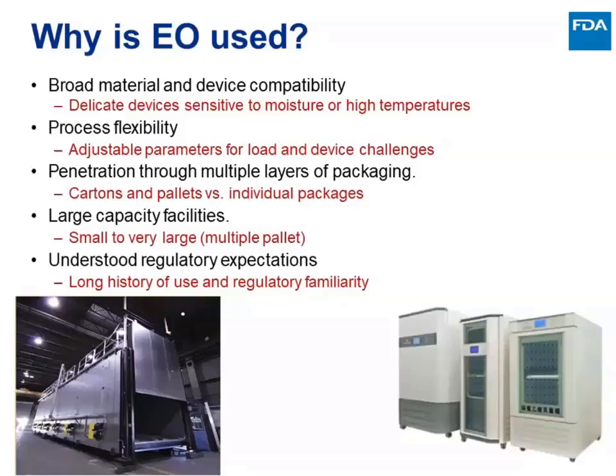The metals obviously can be used in an autoclave with pressure and steam, but the plastics of various sorts have been sterilized by ethylene oxide, and it has been done on an industrial basis, primarily in these kind of units on the left, where you put whole pallets into these units, and they then are sterilized. So devices that are being sterilized this way are delicate devices, sensitive to moisture or high temperatures.